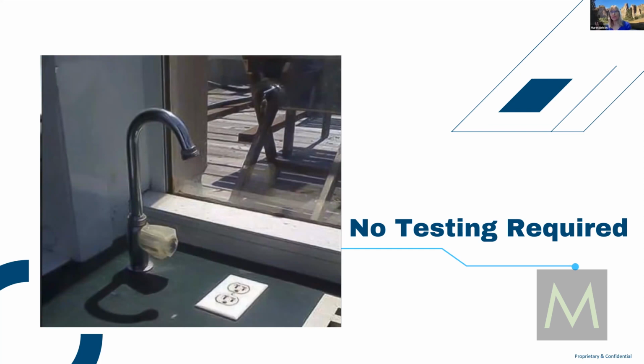I agree with all the comments made earlier about testing to standards and making sure that the company identifies the requirements. I also just wanted to note that not all the verification required for a standard is testing. In some cases, the clauses ask for things like, do you have a quality management system, or do you have a risk management procedure? So some of the clauses in the standards, the test houses aren't going to be able to do for you. The company actually has to get the verification results for those.